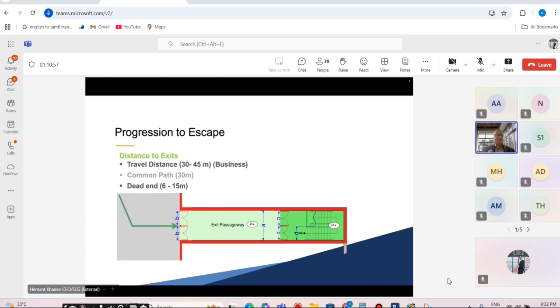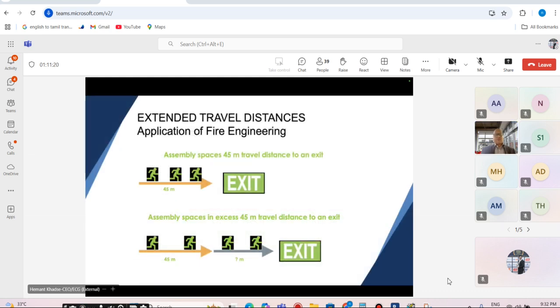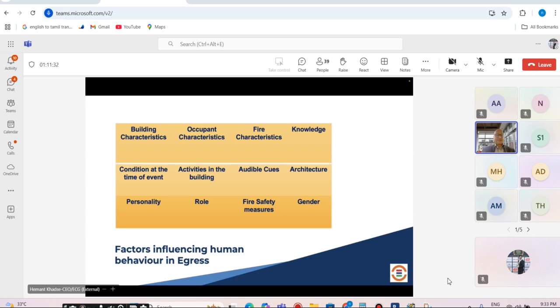It's a path where you are actually using a distance, but thinking it is an exit, it is not an exit. So you have to turn back and then go to the appropriate fire exit. So that's a way to look at your common path and dead end. Every occupancy has very clearly defined what's my common path and what's my dead end, and accordingly you'll have to see it. But if it is going to exceed the regulated or prescriptive limits, there is a performance-based standard which can meet your life safety objectives.